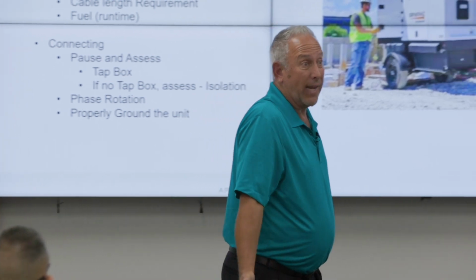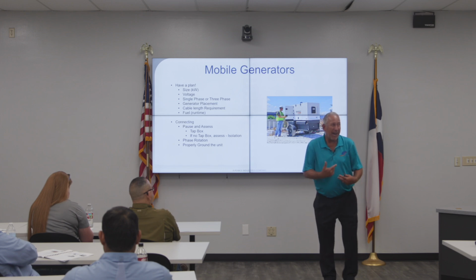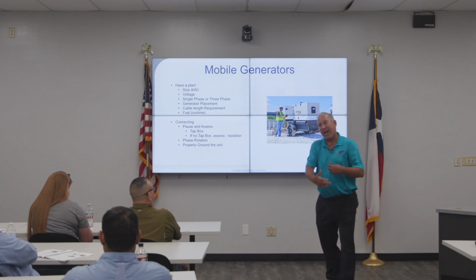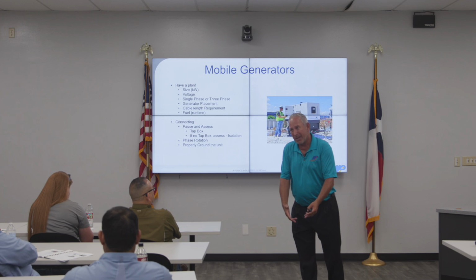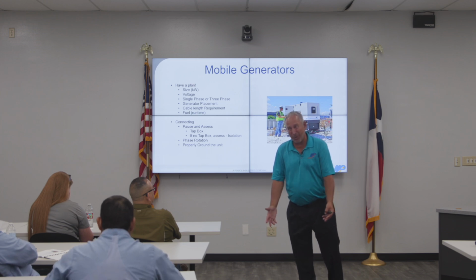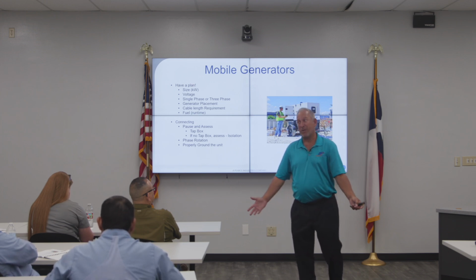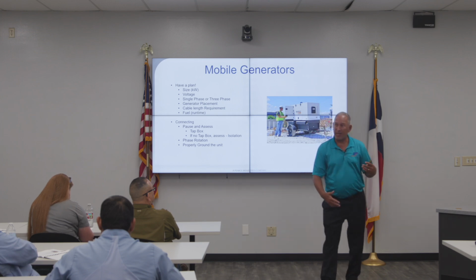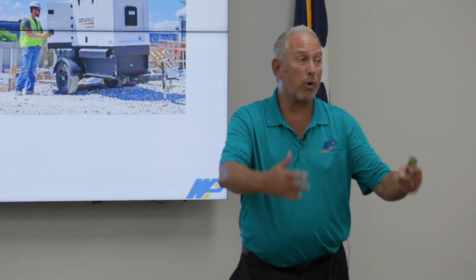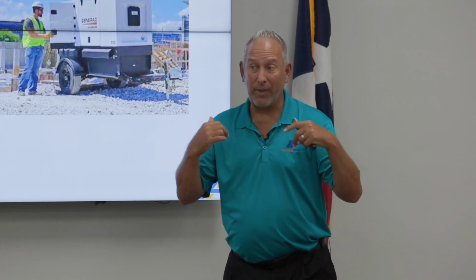If you're going to do load testing all the time, put provisions in for load testing. Don't have some technician dropping your cables every time to hook up a load bank to test your generator. Because when he left, did he do it right? Did he check his connections? I commissioned the site, but if someone went in after me and started playing with load bank cables, I'm like, is it back to the way it was when you found it? I don't know. So if you're going to be testing, make provisions for it. But on the roll-up mobile side, that got serious.